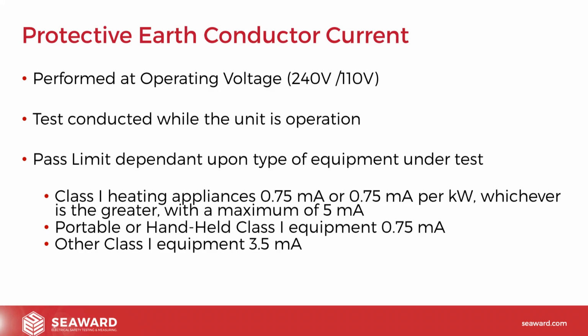correct pass limit is. And you'll see here, for anything that's class 1, that's a heating appliance, so any of your red rads or anything like that, we're typically looking for a pass limit of 0.75 milliamps per kilowatt. So you simply multiply 0.75 by however many kilowatts the heater is, and that will define your pass limit. Now, the Code of Practice does recommend a maximum of 5 milliamps. So if your calculation goes higher than that, we should still apply a maximum limit of 5 milliamps.